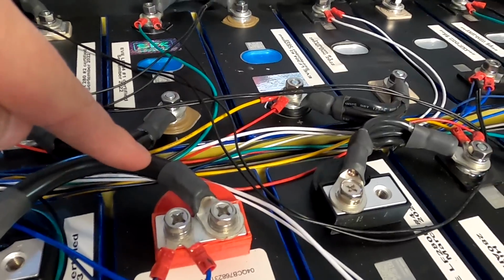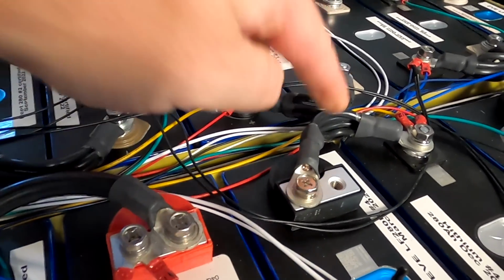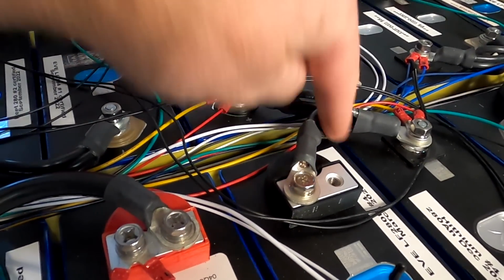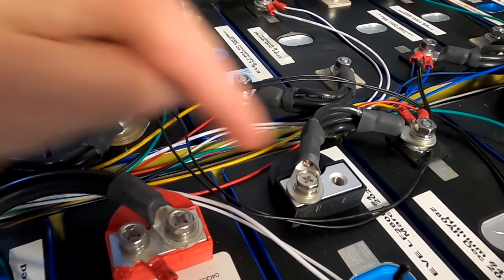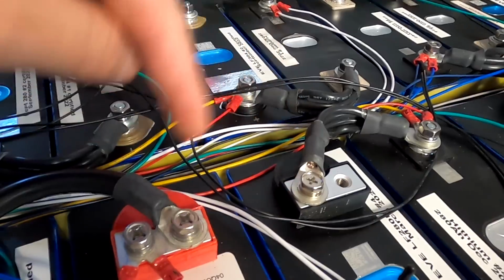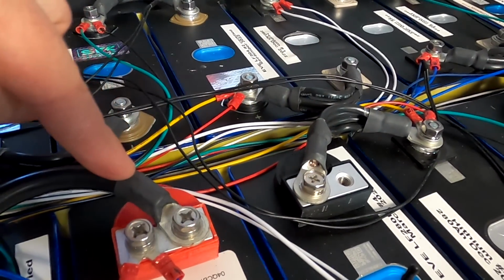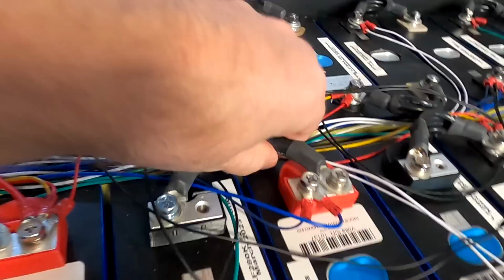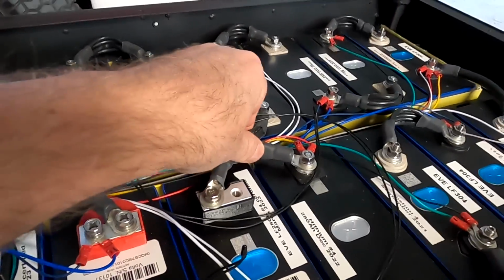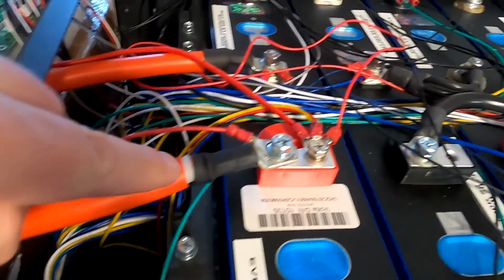Yeah, here you can see these 2 bus bars again. This is 1 solid cable, and these are 4 separate single cables, but they are crimped into 1 ring lug, same as this one here. But this one doesn't heat up as much as this one - that is interesting. Well, it's not even warm, it feels cold. Yeah, this is probably a bad crimp here.